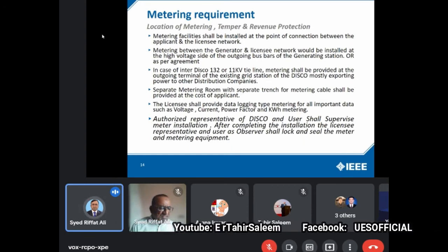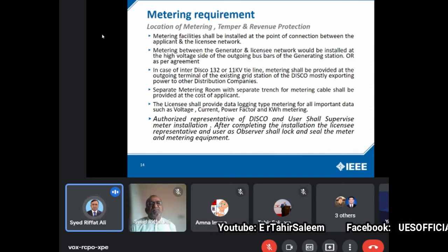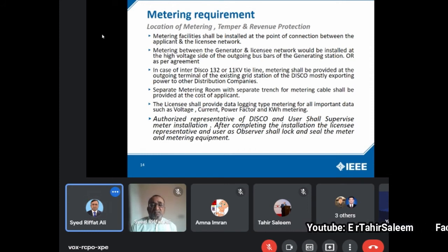While the practice for bulk supply consumers is that, even if they have their dedicated feeder, the metering is at the consumer end as per their own specification. A separate room is provided by the consumer to the DISCO authorities. The licensee shall provide a data logging type meter for all important data such as voltage, current, power factor, and kilowatt hour metering. This we will examine in the next slide as well.